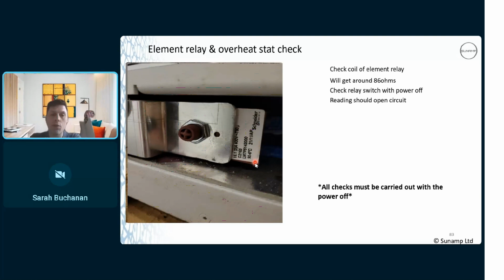So if you're getting a constant tripping, then the relay would be my first port of call, if the battery's been in for a while, that is. But that's a little cross button there. If anybody ever worked on an older Worcester boiler, an old Ranco overheat stat, that's what that is. This was made by Schneider. Terrible name for a company, as far as I'm concerned. But if it does trip, the little crossy button will pop out from the round housing.